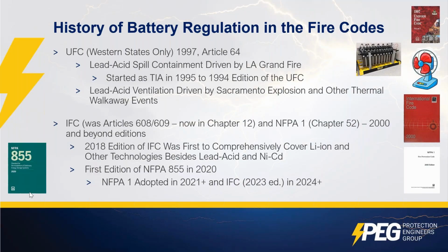So no one was hurt, but there was an explosion caused by basically battery abuse, where they really just tortured these batteries and caused an explosion. No one injured, but that drove some other concerns that ventilation systems should be monitored by fire alarm type systems and reported to central stations and so forth. So, all these events do play into the code. Whenever there's a fire, an event, an accident, it does ripple through the code and get implemented.